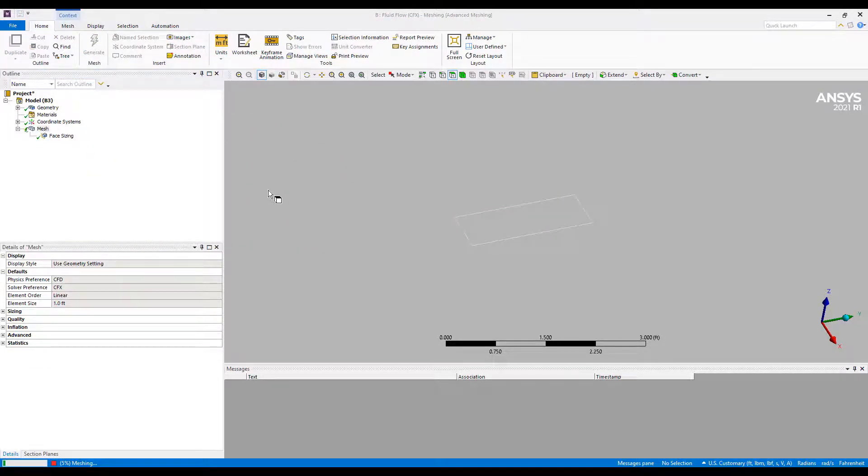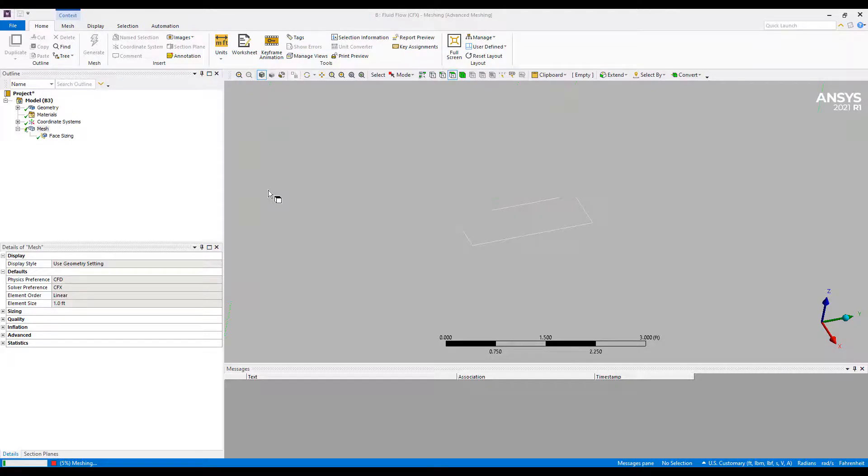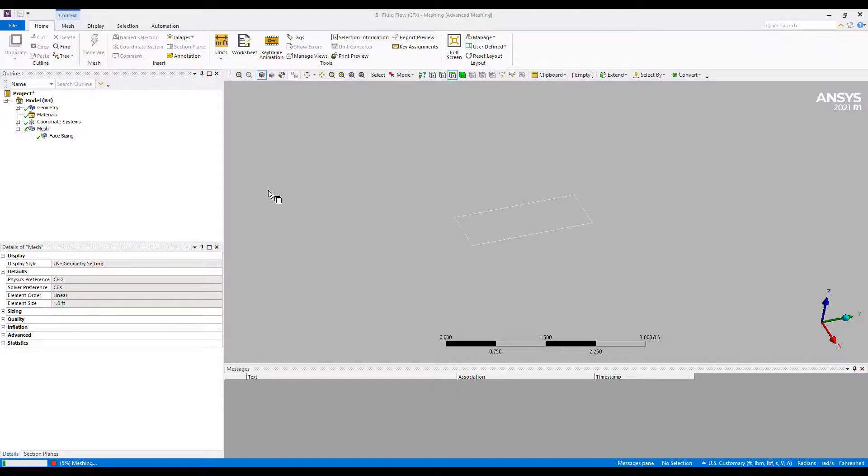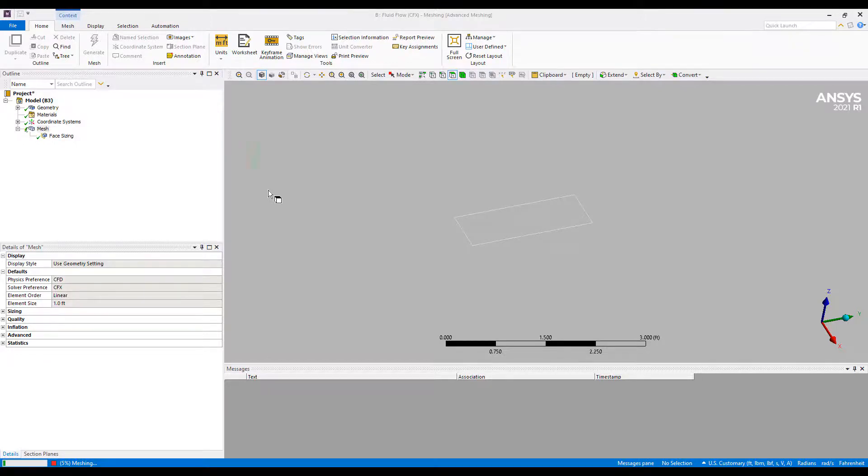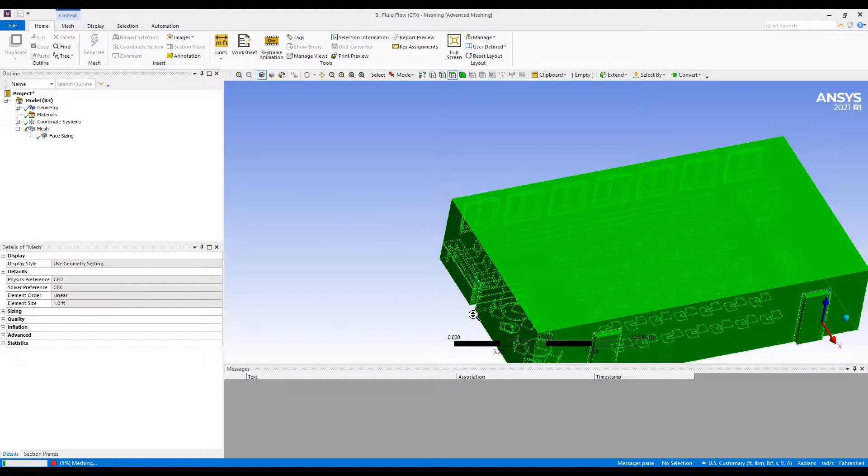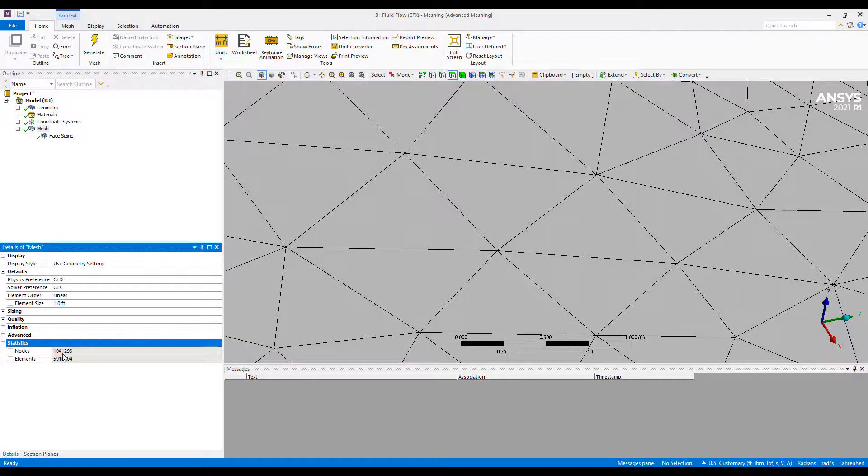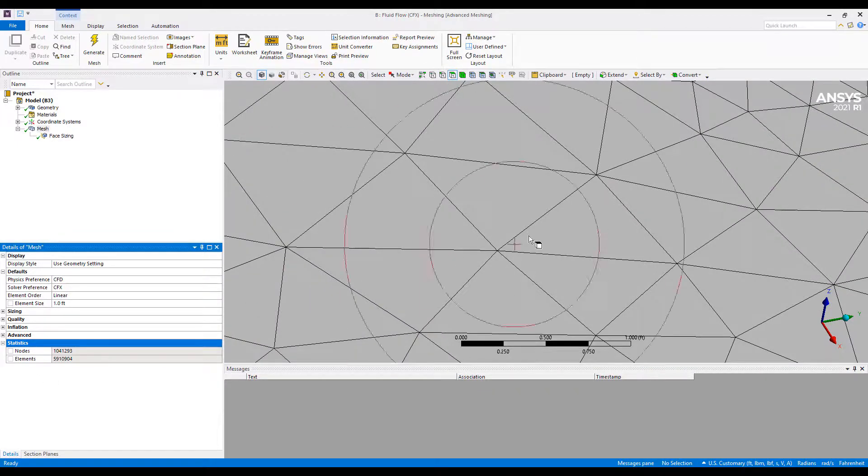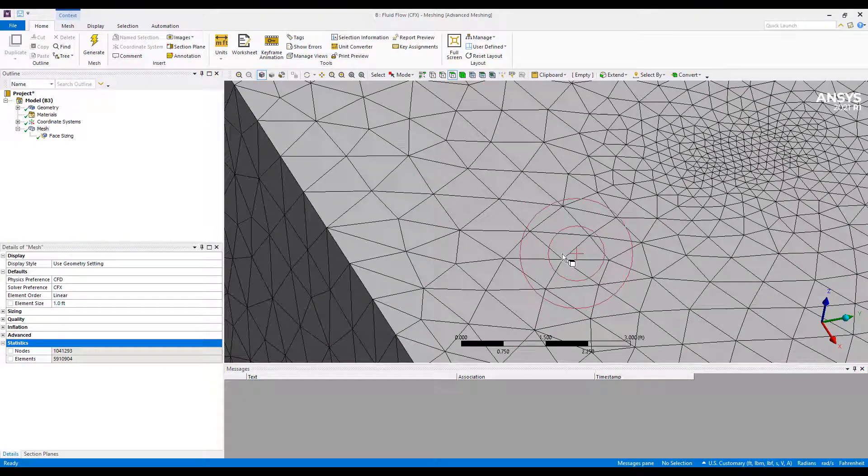And go ahead and generate a mesh. Since we're just tracking the air movement in this room, we don't have to be too careful with the meshing. But certainly we can add things in like inflation layers and boundary modeling to try to capture detailed airflow patterns. We can do some of that later on too. The mesh we created here is about a million cells. This is enough for the current simulation.